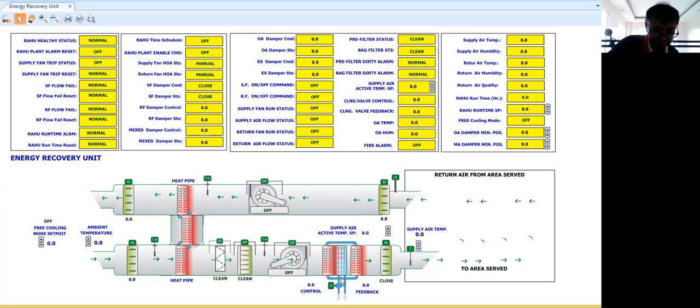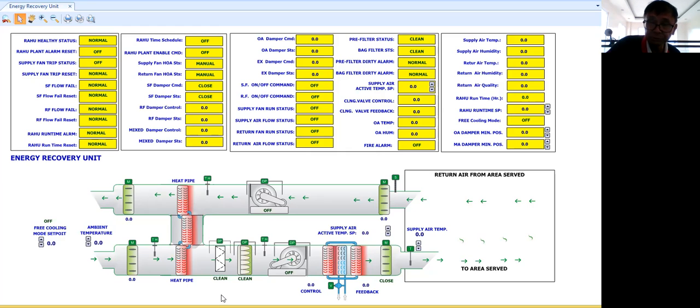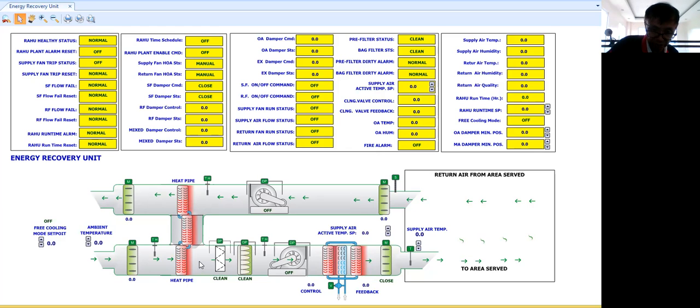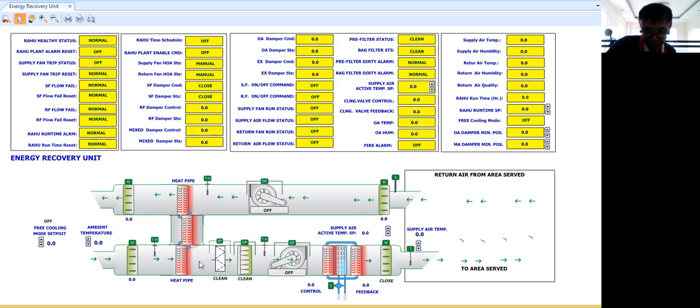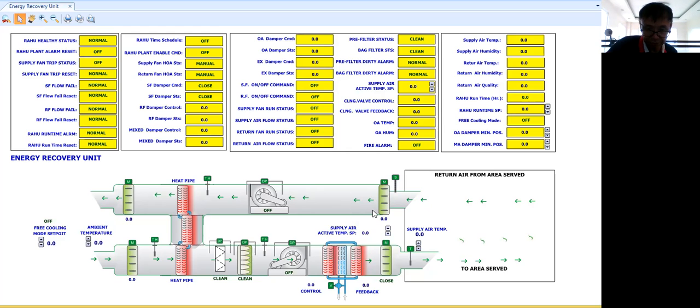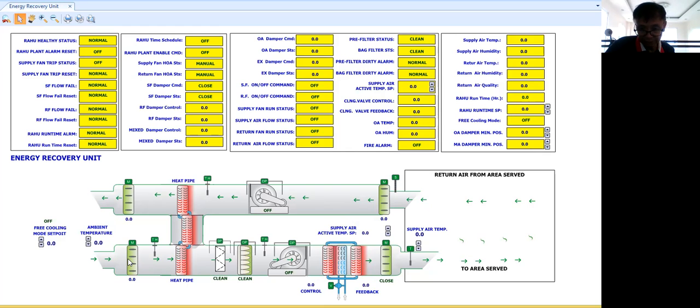Now again, this heat pipe, it doesn't have any moving parts. So it's very easy to maintain because there is no moving part and it has a long life because there are no moving parts again. Now here, the energy from our exhaust air stream or our return air stream is being utilized by our heat pipe to bring down the outside air temperature a little bit lower than the ambient temperature. So again, the same purpose here.